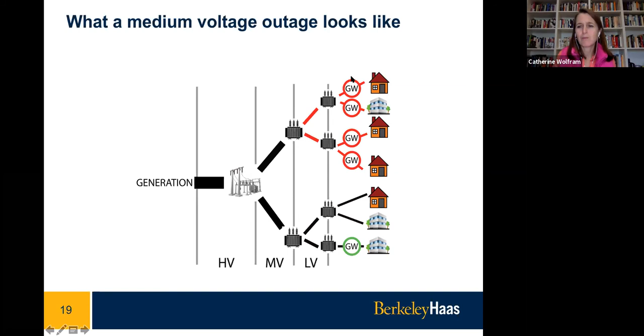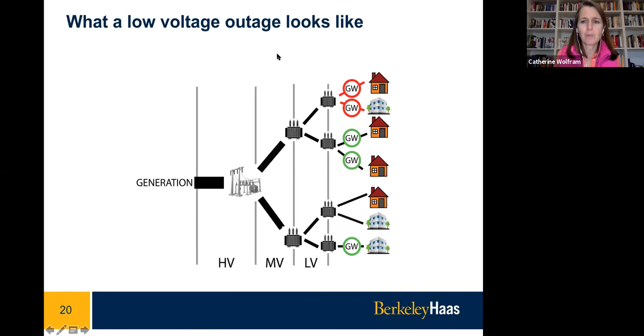Similarly, if you see 4 devices go down, and you've mapped them to transformers on the same feeder, you can say there's a medium voltage outage. And if just 2 devices on the same transformer go down while 2 nearby devices on a different transformer don't, you infer there's not a high-level outage. They found that deploying about 3 devices per transformer gives very good visibility even into low voltage outages - too few and you confound someone unplugging a device with an actual outage, so you need redundancy built in at the transformer level.